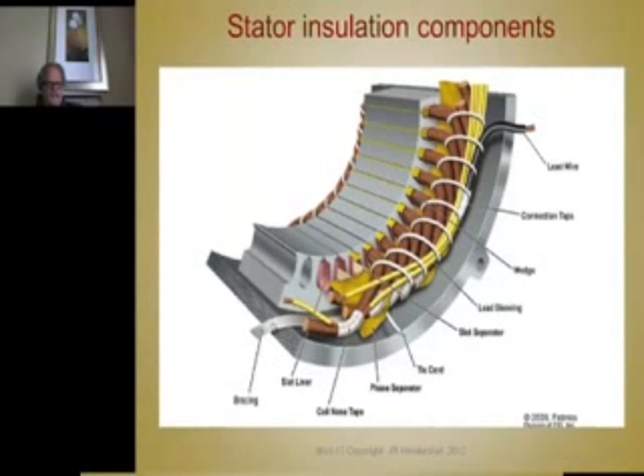And then this is a strip that goes around here for bracing. That gives rigidity to this mass of end turns. So if you wrap this bracing strip around here, and then you go through the lacing process of the tie cord, it laces all these end turns and the leads and the pigtails to this bracing strip around the outside. On bigger machines, this will be laced to maybe a steel insulated ring that I showed you on one slide in the last lecture, or it can be attached to steel blades that have been welded to the end of the core to support these end turns.